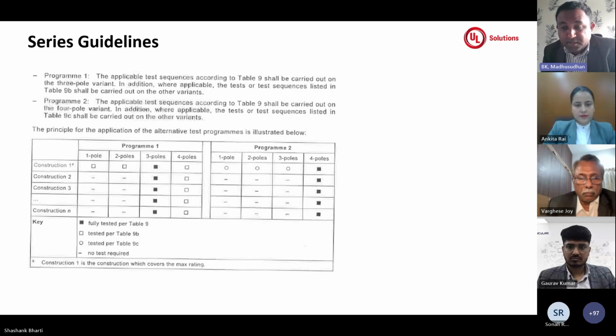Also, if there is a series of range which has multiple construction breaks within the range, then the standard allows selecting one construction as the maximum range, which will fit within the range for the majority of the products. For the other constructions that fall under the next nearby constructions, for construction 2 and 3, we can do only 3-pole testing, and the rest can be waived off. Since you are selecting 3-pole in program 1, you need to do additional testing for 4-pole. With that, we will be covering the complete range. That speaks about the requirement from program 1.